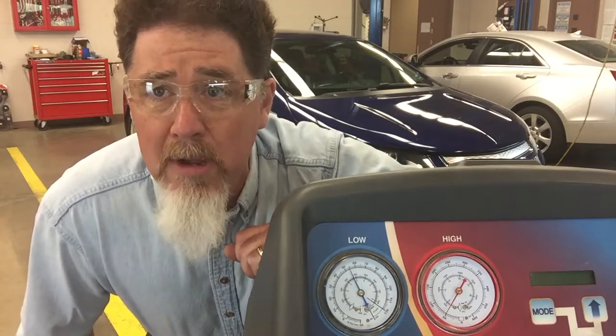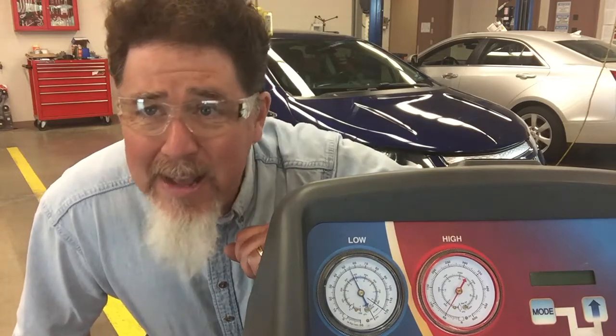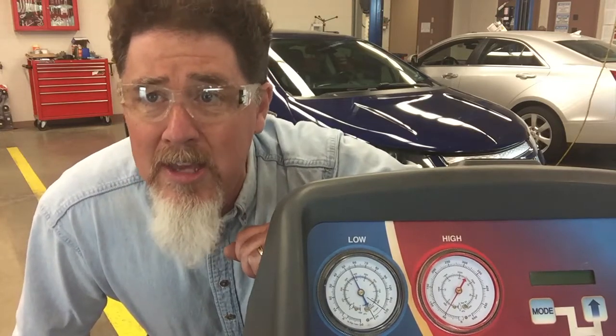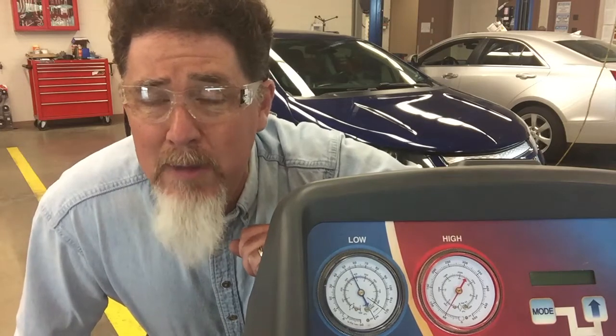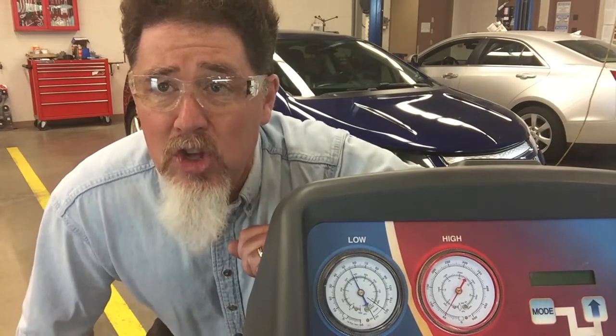Everything is operating normally. If it was taking 5 minutes to equalize, we've got a restriction somewhere in the system. I would be looking at the orifice tube as my first area as a restriction.